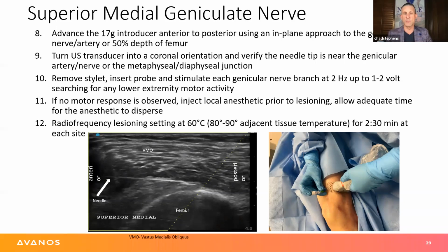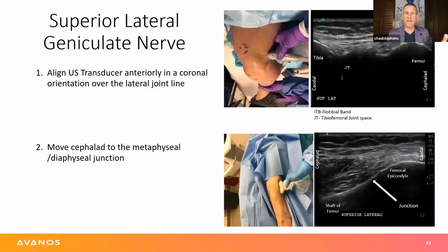And you can do the ablation there just like any other ablation where you ramp up the machine, do your motor testing. You do up to 2 hertz there to confirm there's no motor activity. And usually there won't be, but go ahead and do it. And then when there's no motor response elicited, you turn the machine to 60 degrees centigrade and you burn for 2.5 minutes. Next slide. So superior lateral.